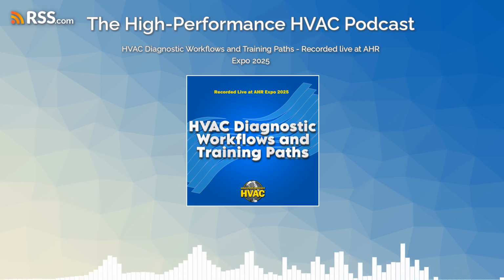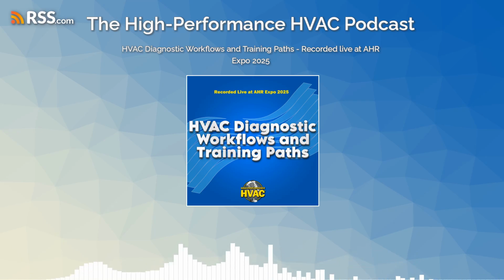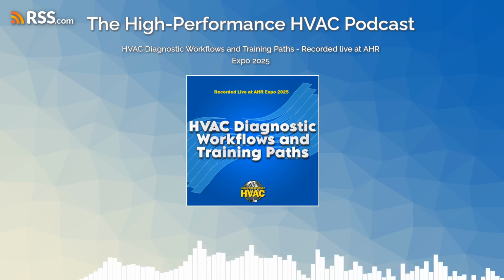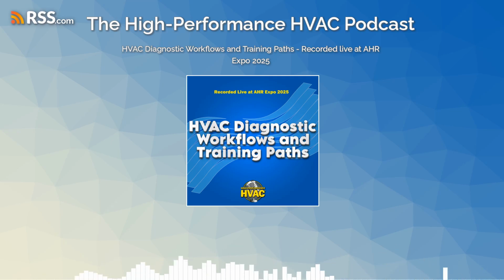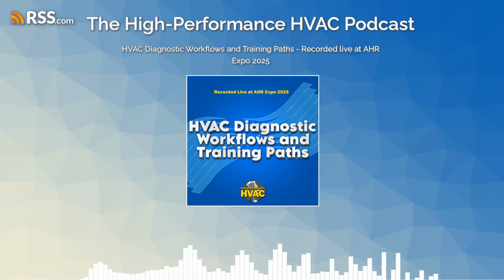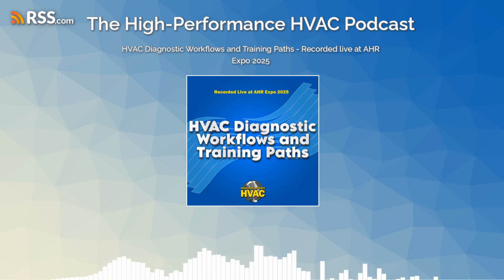Sure. So Rob Falk, who's one of the founders of NCI, took it on as a project, and actually it was John Purrier, I believe, to collect fan data from literally hundreds and hundreds of units. And then we were able to come up with sort of an average. So it's not right on, but here's what a typical unit might have in terms of external static pressure ratings, and the calculated fan airflow, if you will, from that table. So that's how we developed the table. And we weren't shooting for perfection. It's more of a diagnostic tool for a service tech.